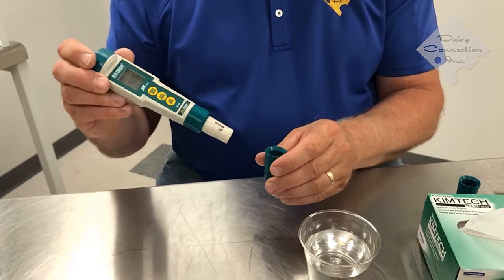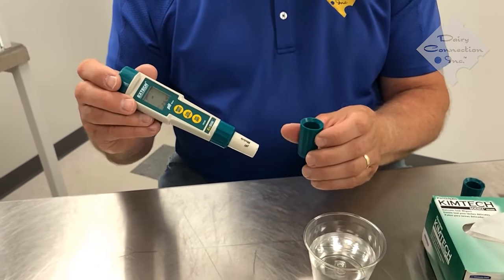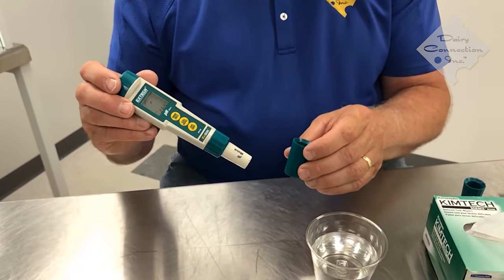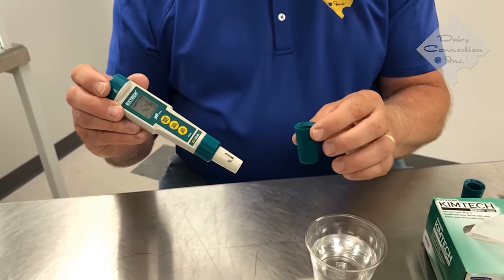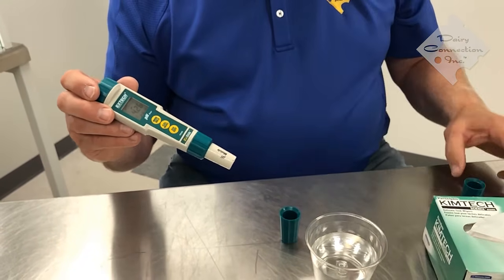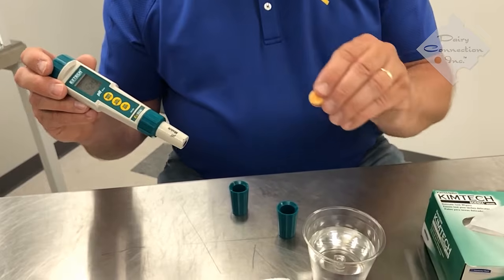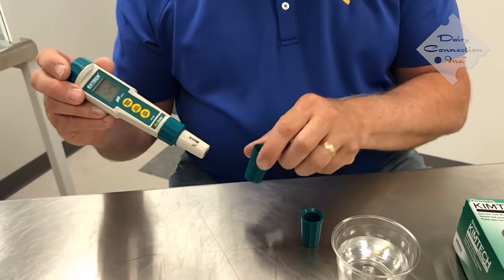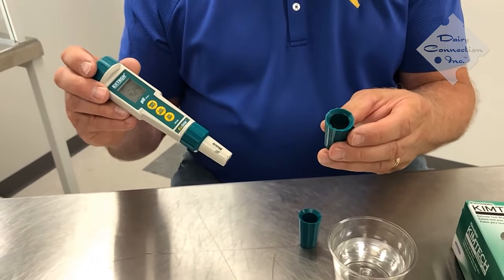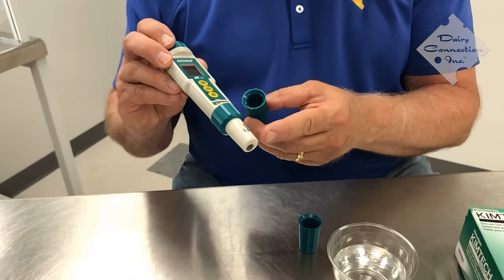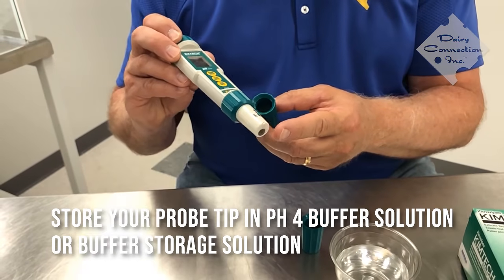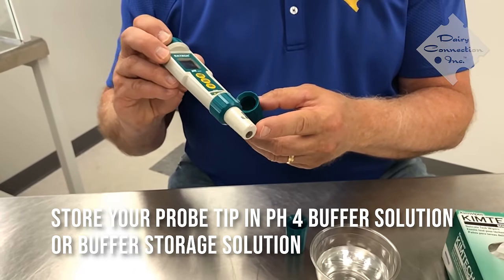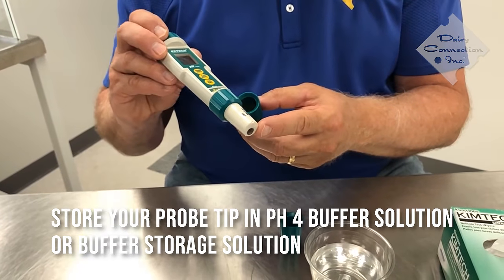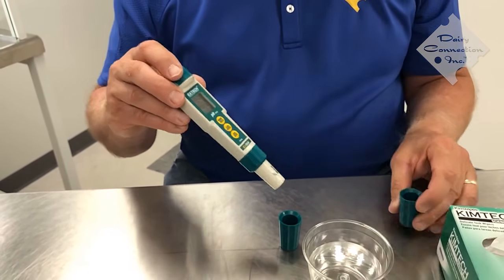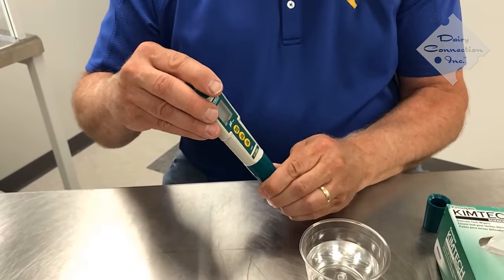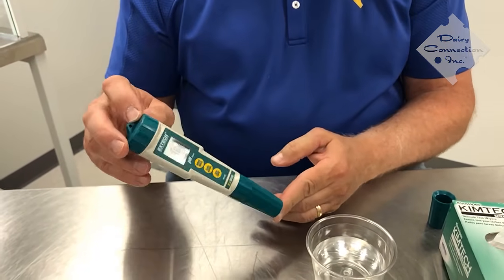So that's the basic concept of the pH electrode. It should be kept wet at all times. When the electrode is delivered, you will see this cap that comes over it. I have another one over here that shows a sponge that is in the bottom of it, and then there's going to be like a pH 4 buffer or liquid to keep the electrode tip moist at all times. If it dries out, you'll have a problem with that, and we'll get into that when we start troubleshooting problems with the pH electrode. But always store it in this liquid, and this is the unit itself.